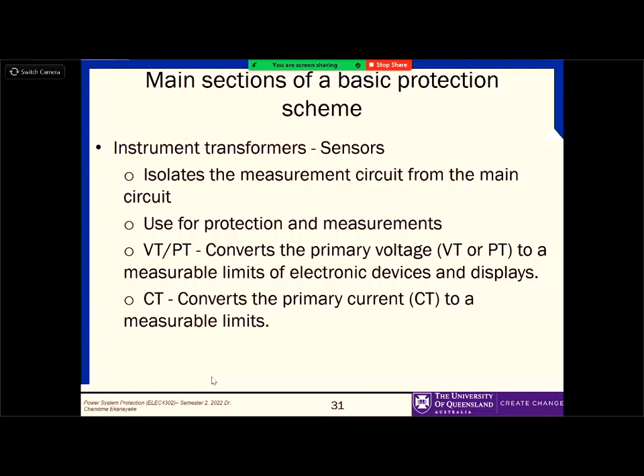That 120 volts can be measured using a normal measuring device. So that helps with two things, for CTs and VTs. One is bringing the measuring quantities into safer limits. The second thing is that your main circuit is now isolated from the secondary circuit. There is no electrical connection, because in a transformer you have separated windings, so primary side voltages or currents will never appear on the secondary side. That helps to isolate those two systems and ensures safe operation. Otherwise, higher voltages would appear at the measuring sites. So those are the main advantages.